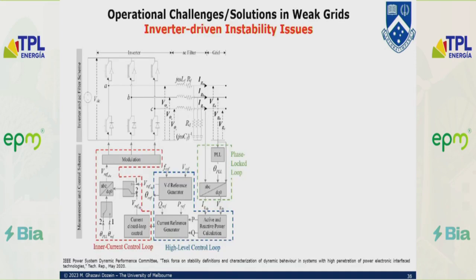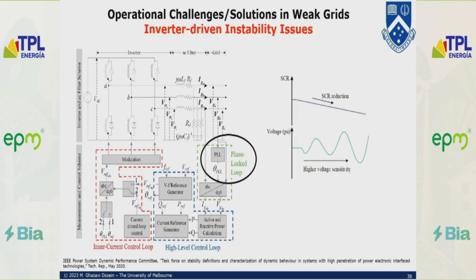This compliance issue primarily comes down to grid-following inverters, when they synchronize with the external system via a phase locking strategy, PLL. If the voltage is very nasty, the PLL cannot estimate the voltage and cannot maintain the inverter level stability.